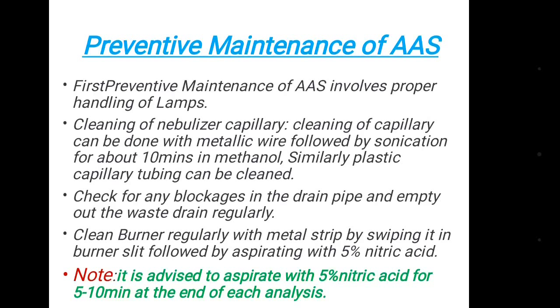Now, preventive maintenance of the AAS instrument. This involves proper handling of AAS lamps, and cleaning of the nebulizer capillary. Cleaning of the capillary can be done with a wire followed by sonication for about 10 minutes in methanol. Similarly, plastic capillary tubing can be cleaned. Check for any blockage in the drain pipe and empty out the waste drain regularly. Clean the burner regularly by swiping a metal spatula in the burner slit, followed by aspirating with 5% nitric acid. It is advised to aspirate with 5% nitric acid for 5–10 minutes at the end of each analysis.